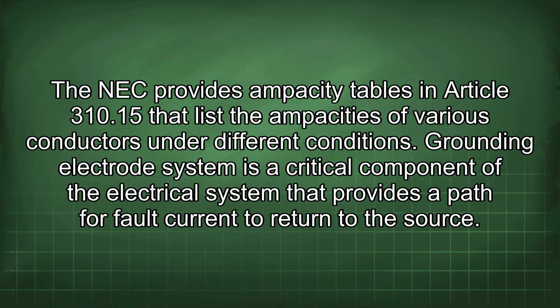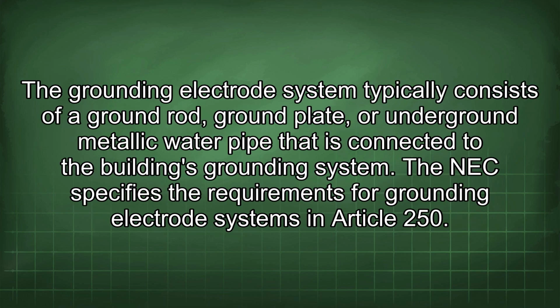Grounding electrode system is a critical component of the electrical system that provides a path for fault current to return to the source. The grounding electrode system typically consists of a ground rod, ground plate, or underground metallic water pipe that is connected to the building's grounding system. The NEC specifies the requirements for grounding electrode systems in Article 250.